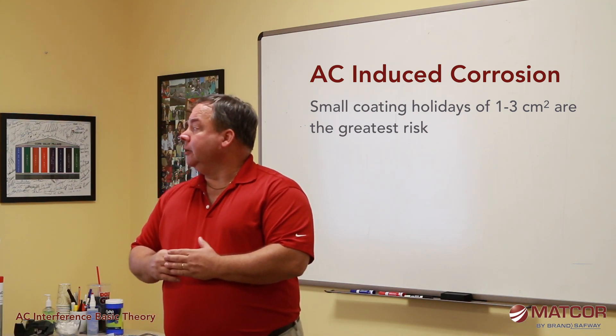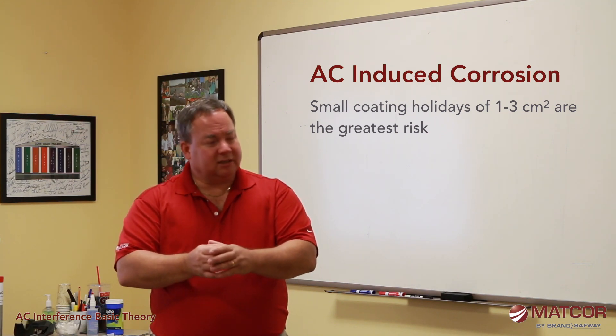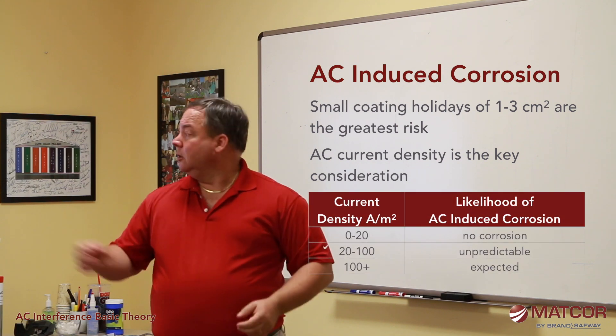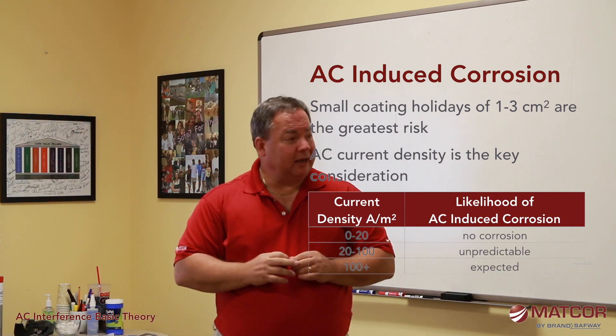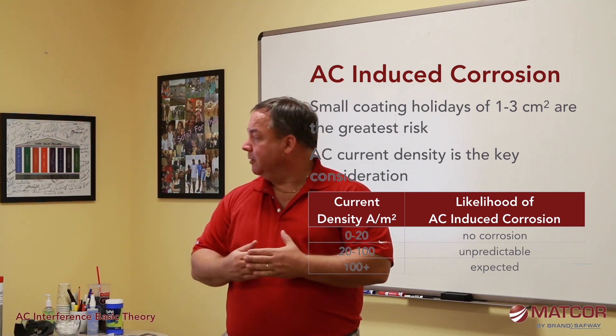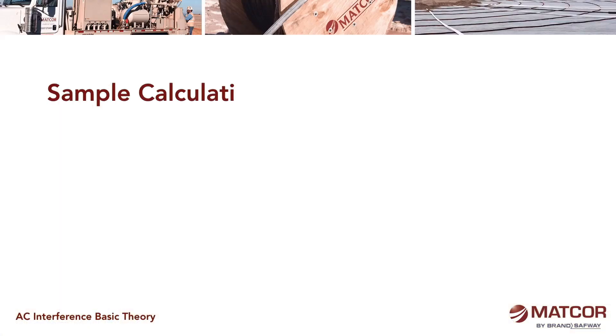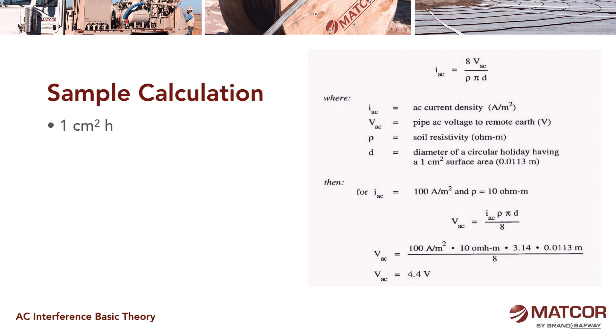It's these small coating holidays where lots of current is being discharged through a small holiday that causes AC induced corrosion. We can measure that — it's called flux — and that's the amount of current over a certain surface area. If we have 20 amps per meter squared or less being discharged off a coating defect, we don't have corrosion. Between 20 and 100 amps per meter squared, we have a corrosion risk. Above 100 amps per meter squared, you can expect corrosion to occur.